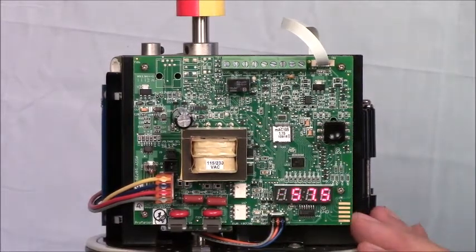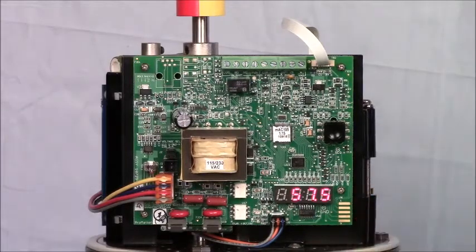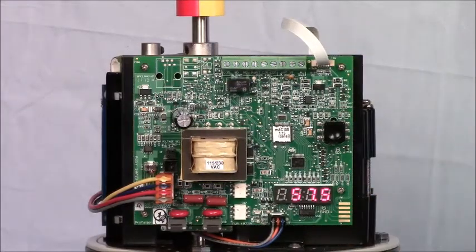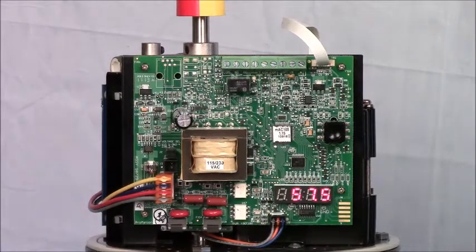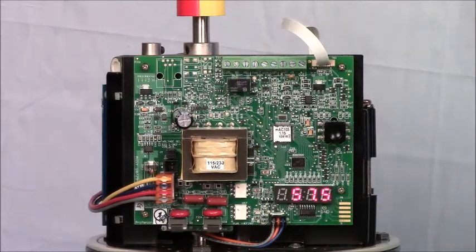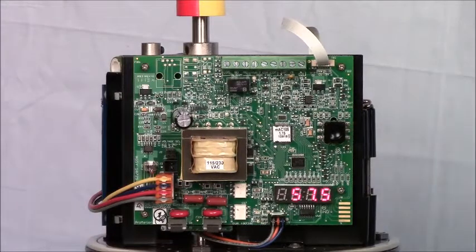The first number that comes up is the position of the valve, right now at 57.5%. But we haven't calibrated the actuator, so we don't know exactly whether it's 57 or 58 or 60.